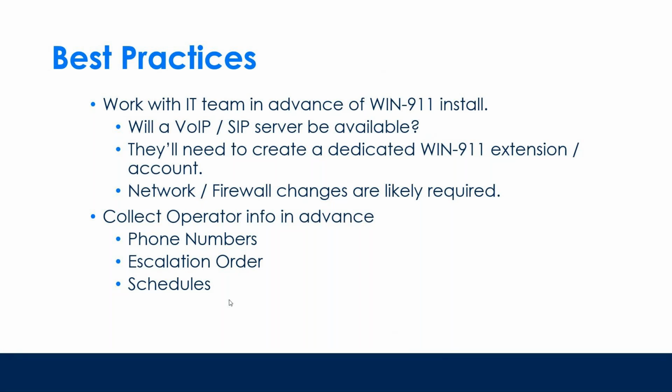Make sure all the network firewall exceptions are made too, like 5060, which is a basic SIP port. What are the RTP port ranges? You need to be able to access those systems from wherever the Win911 system is. And almost every time someone goes out there to set it up, none of these changes have been made. So it can take a long time to work with an on-prem VoIP server if it's not set up ahead of time. So it's a great idea to contact them before.